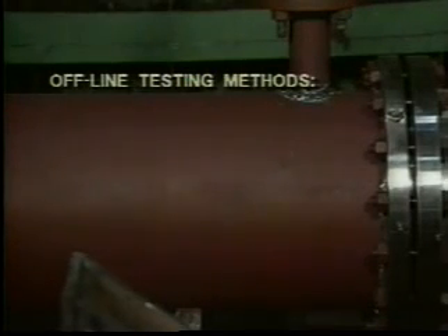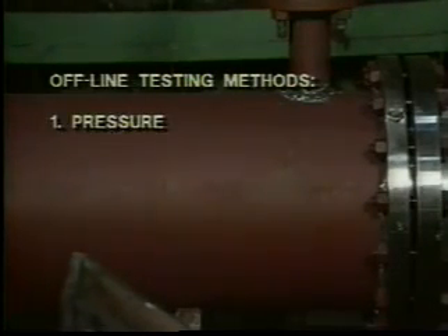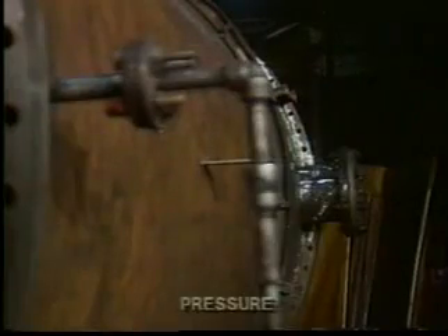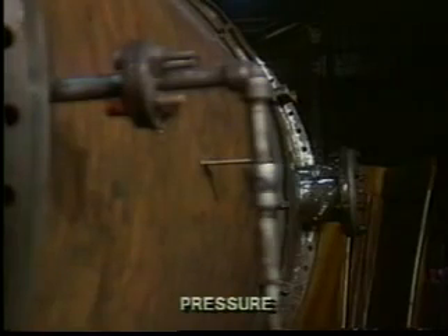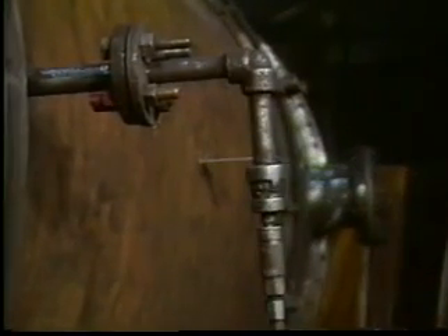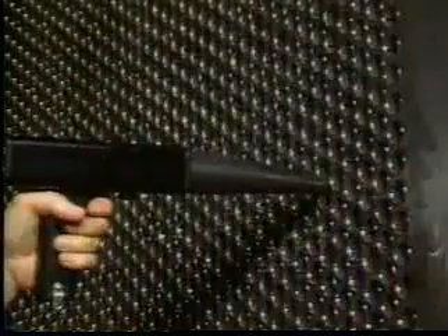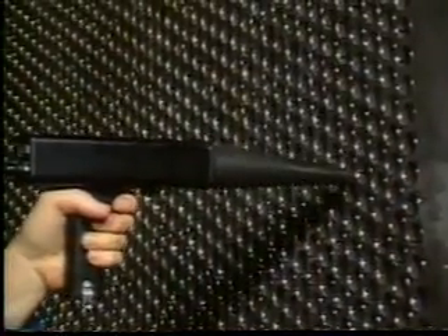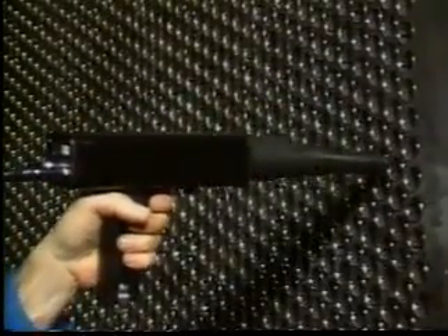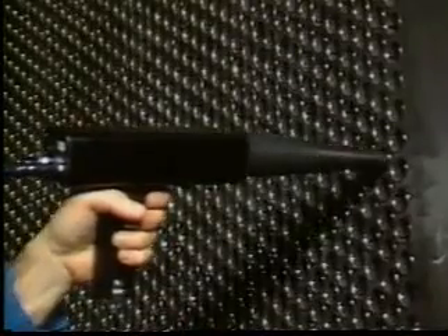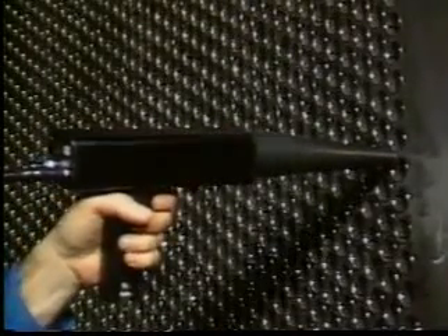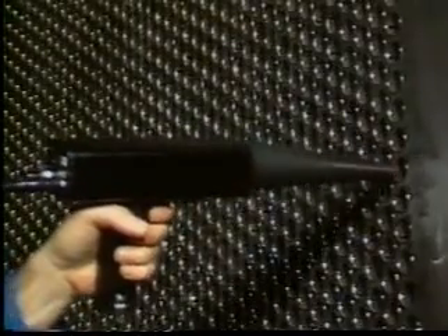In an offline environment, three methods for testing tubes are used: the pressure, vacuum, and tone methods. The pressure method is conducted by first sealing up outlets to prevent the gas from escaping and connecting house air to the inlet. The system is then pressurized. Test the system as previously demonstrated. Listen for the characteristic rushing sound of a leak with the ultraprobe scanning module. Once the general area of the leak has been found, insert the rubber focusing probe and compare the sounds to neighboring tubes. A leaking tube will produce a louder sound. Test both ends of the heat exchanger.